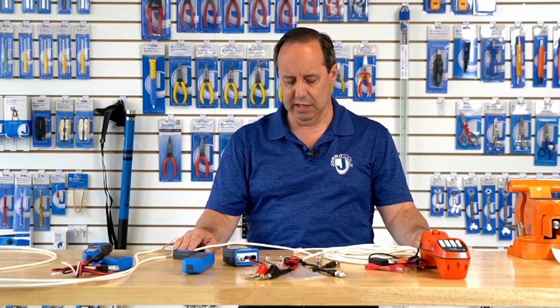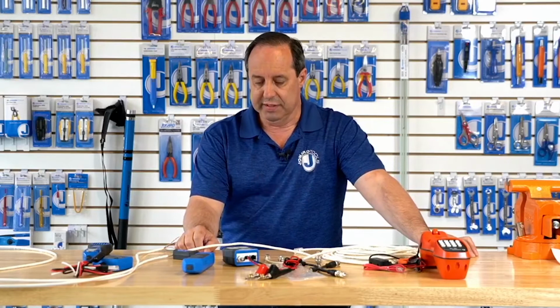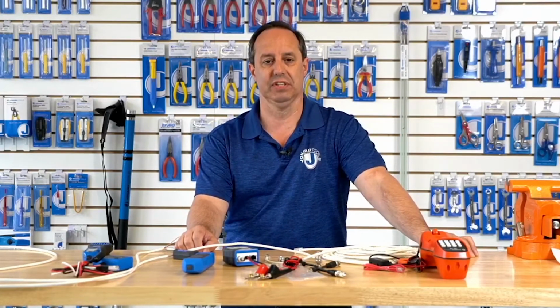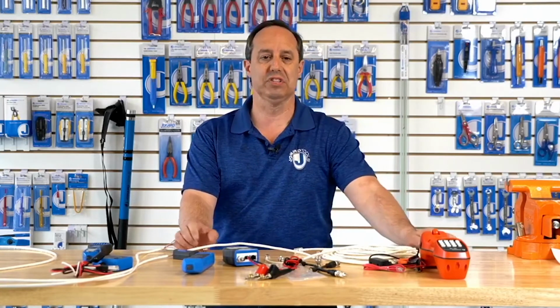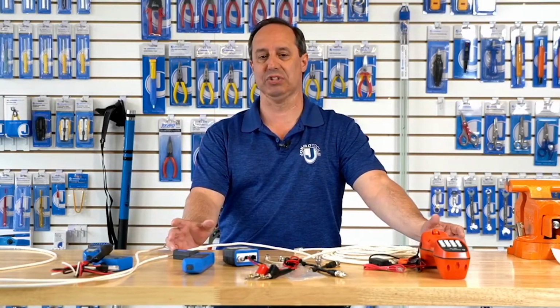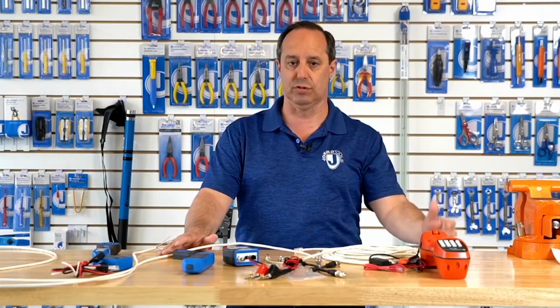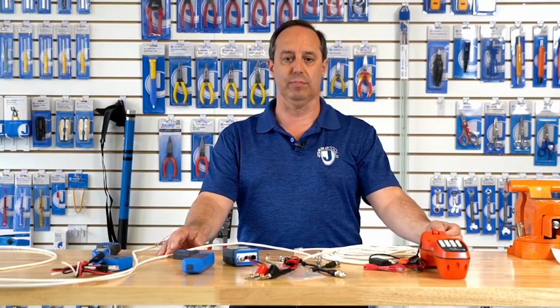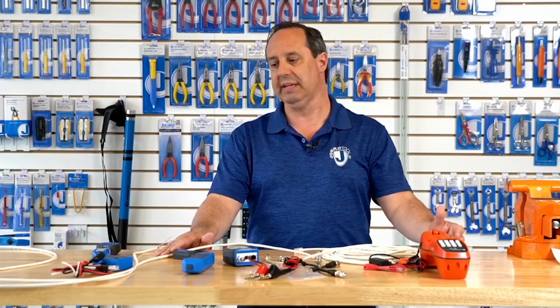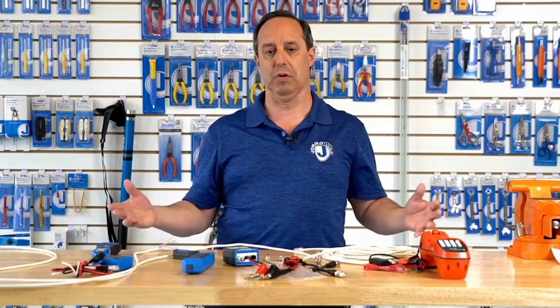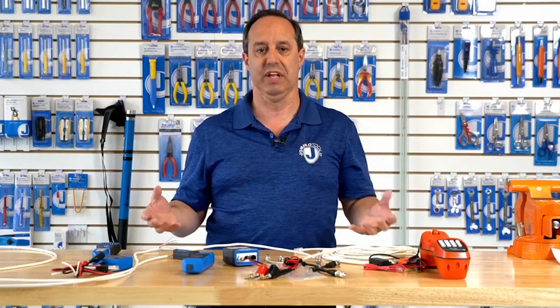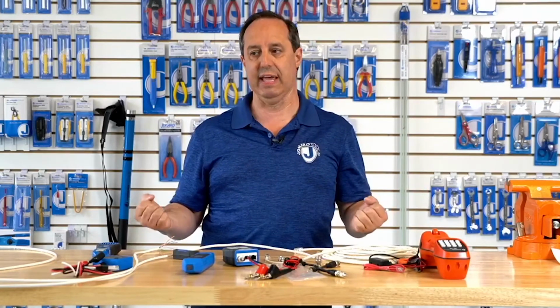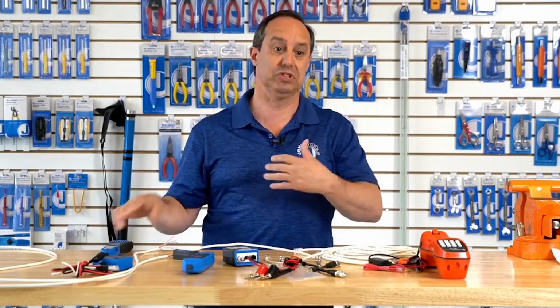Interesting question: can I use this on armored cable? The issue is that the armor acts as a shield, and since you're trying to put a tone down the center of the cable, the armor shields the tone from getting out, so you won't be able to sense it. If you're stuck in that situation, make sure the cable isn't live, then disconnect the shield from ground so it's floating and no longer trapping the tone inside. Now the probe will be able to sniff it out.